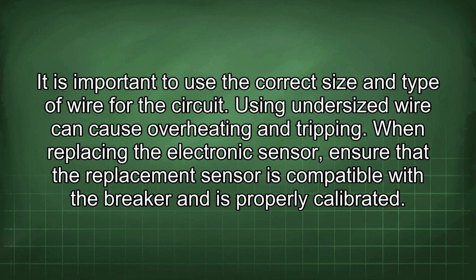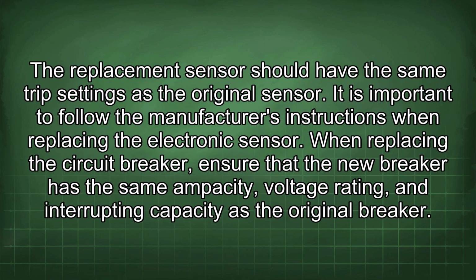When replacing the electronic sensor, ensure that the replacement sensor is compatible with the breaker and is properly calibrated. The replacement sensor should have the same trip settings as the original sensor. It is important to follow the manufacturer's instructions when replacing the electronic sensor.